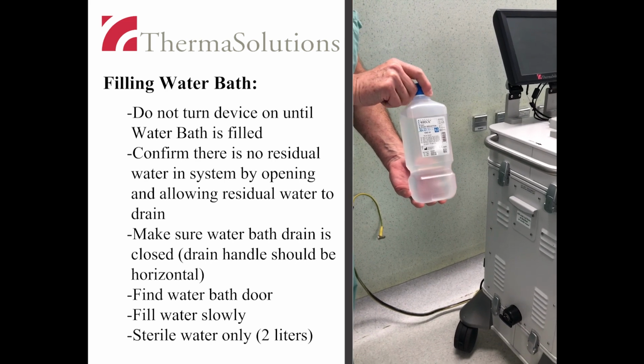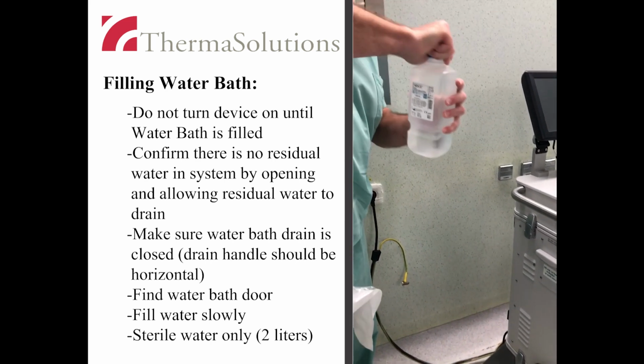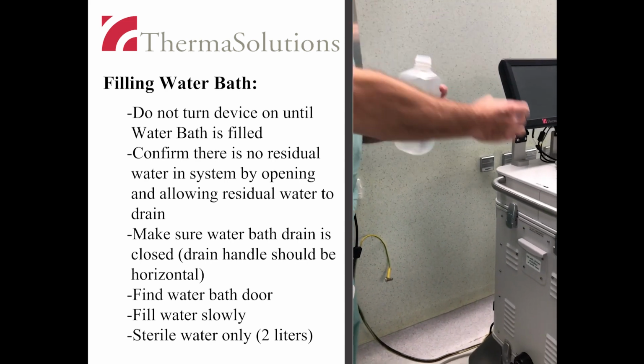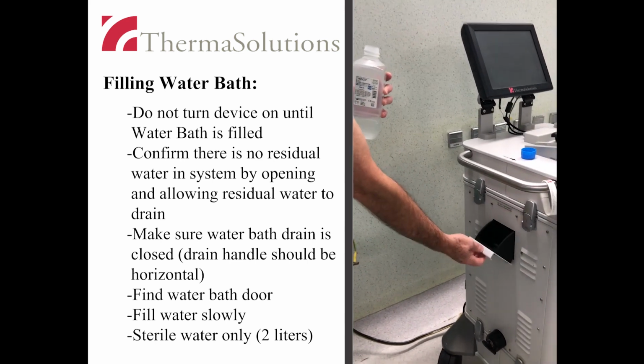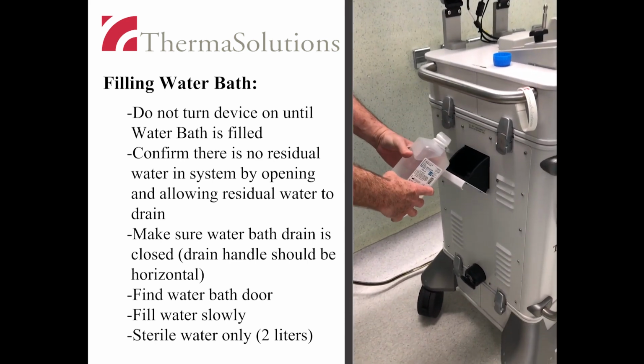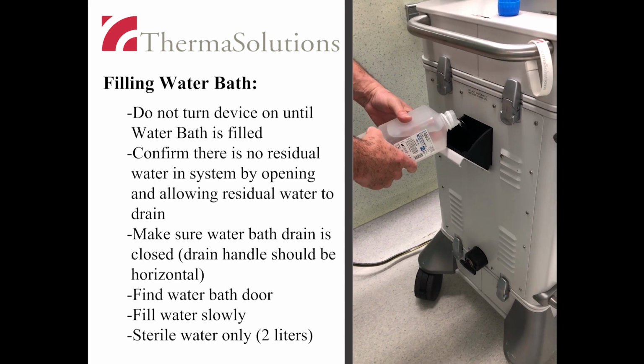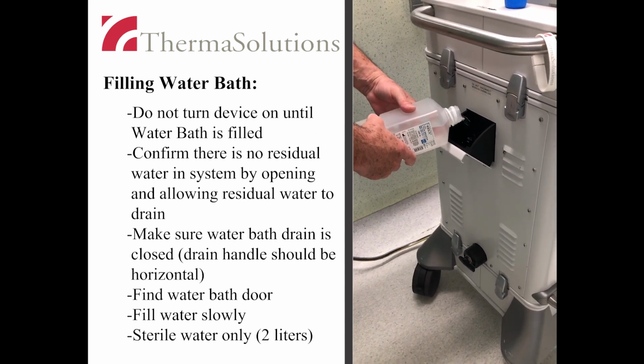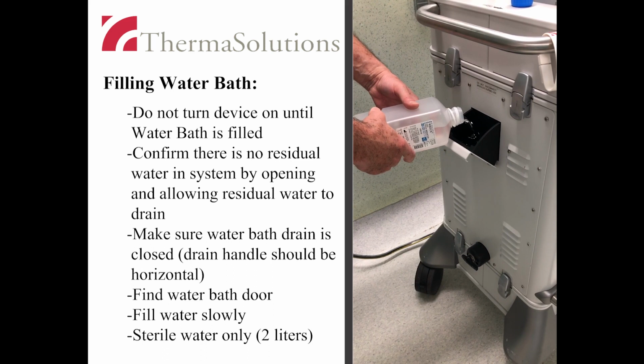The water bath should be filled prior to powering up. Open the water bath drain first to confirm the water bath is empty and have a basin to catch any residual water from a previous case. When the drain tap is closed, open the water bath door and slowly fill with 2 liters of sterile water.